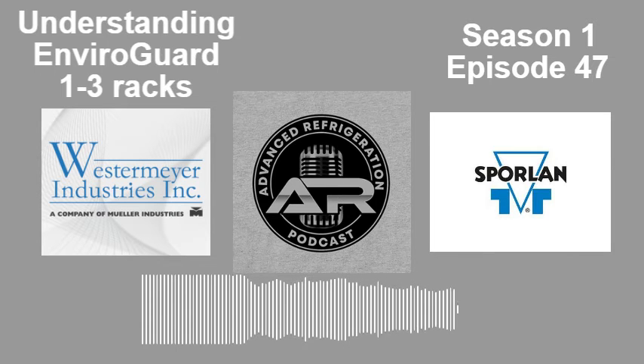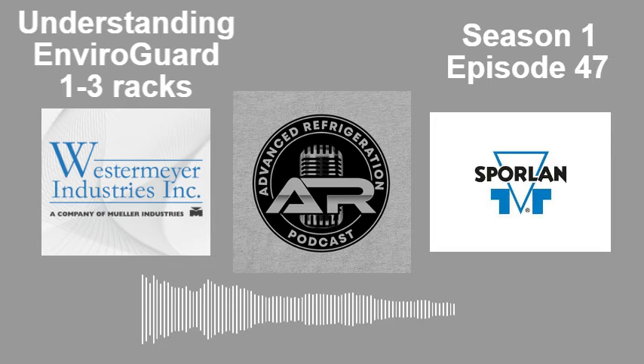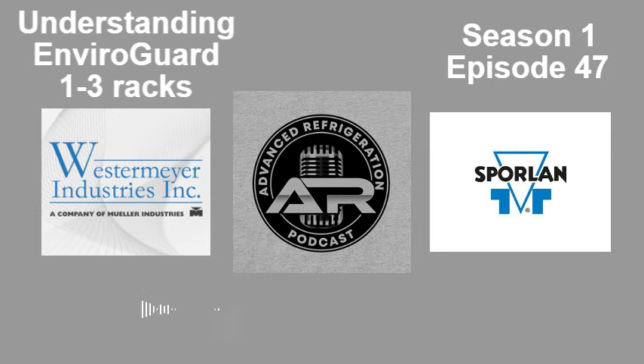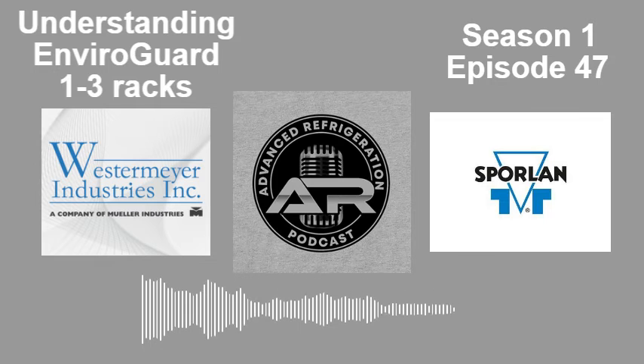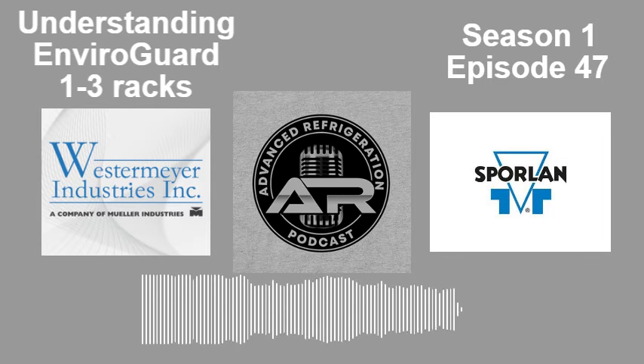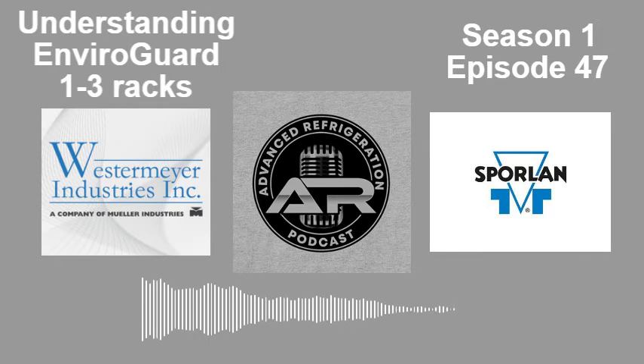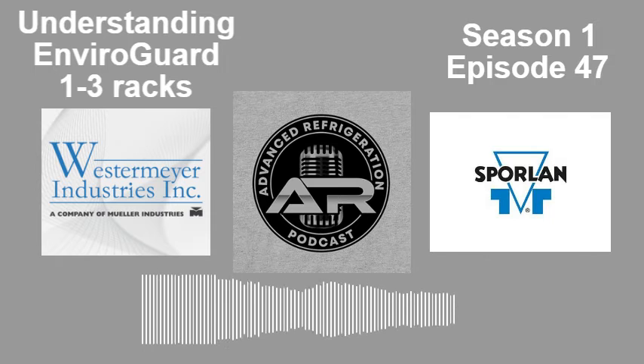I was just asking because I know how most national chains, they're very particular on the way they're programmed. So if you try to tell a second party programming company that this is the way it should be done, they're going to tell you to go pound sand. That's not the way. We have 30 other stores in the area, and all 30 stores run like shit. Yeah. And then this is very similar to how when we start getting into the SR racks and we talk about the Costco style racks, it's very similar to that. Theirs goes a little bit more in depth with it because they have a little bit more control the way they're doing theirs. But that's how I ran mine.